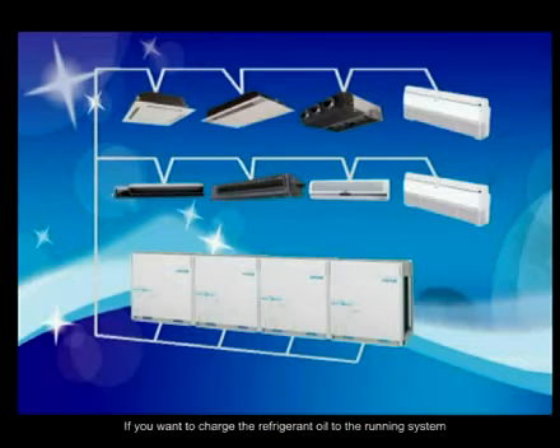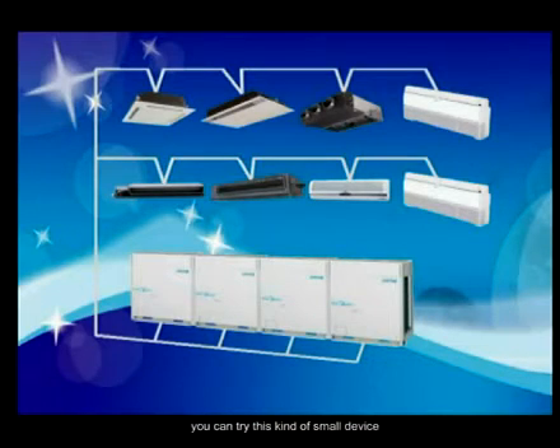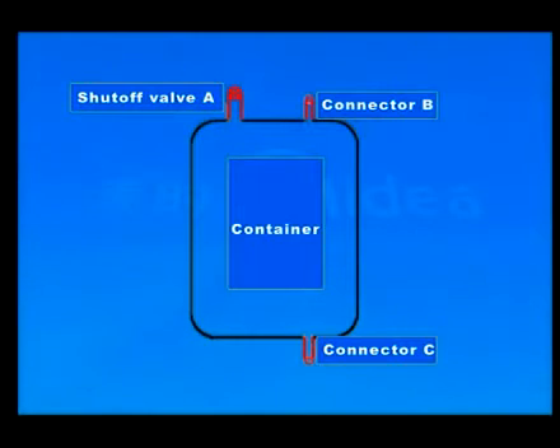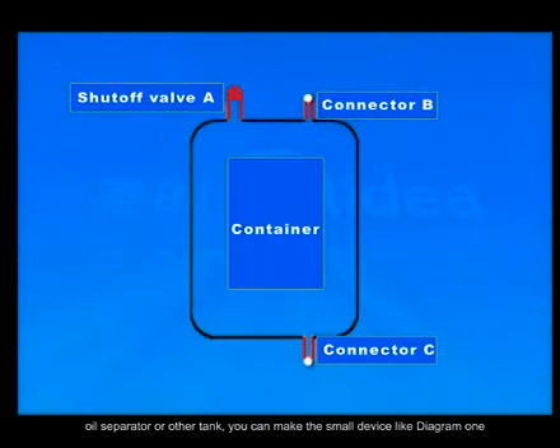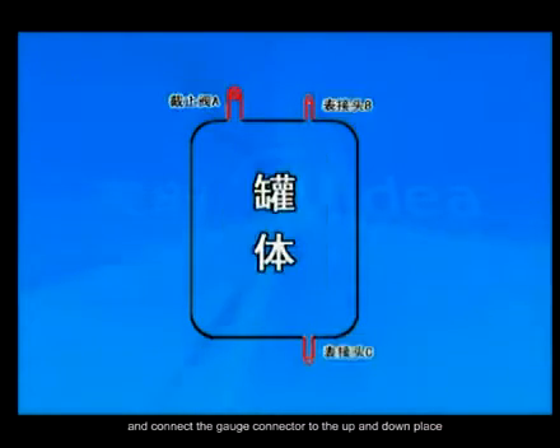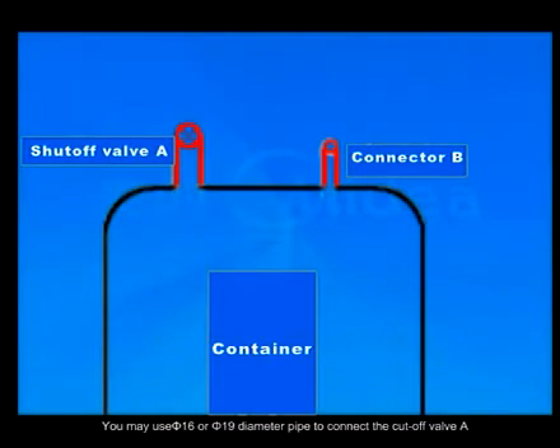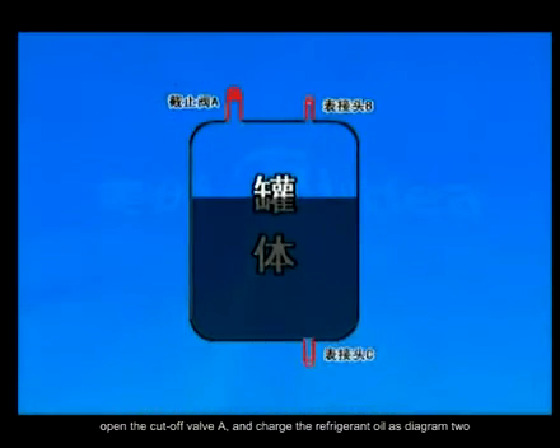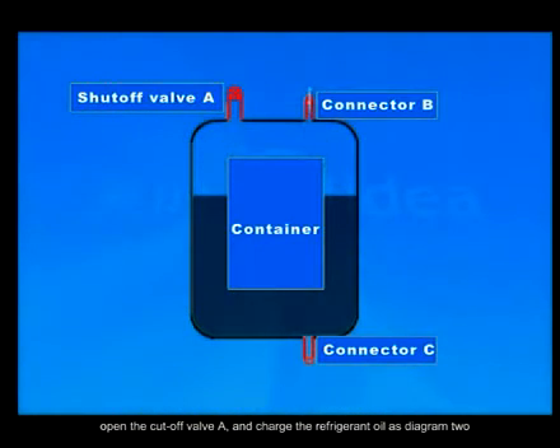If you want to charge refrigerant oil to a running system, you can try this kind of small device. Using a small refrigerant tank, low pressure tank, oil separator, or other tank, you can make the small device like diagram 1 and connect the gauge connectors to the upper and lower places. You may use a Phi 16 or Phi 19 diameter pipe to connect to cutoff valve A. Open cutoff valve A and charge the refrigerant oil as in diagram 2.